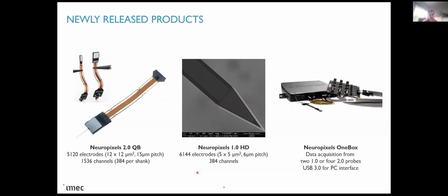We have also released a device that we call Neuropixels 1 HD. So this probe has a very high density electrode array. Here, the electrodes are much smaller, 5 by 5 microns, with a pitch of 6 micrometers. So this allows recording from smaller cell sizes, and there is already a preprint of a paper. There was also a poster at the event that described the kind of observations that we can make with this probe. So in total, we have 6,144 electrodes in a single shank, with still the limitation of only recording 384 at a time.